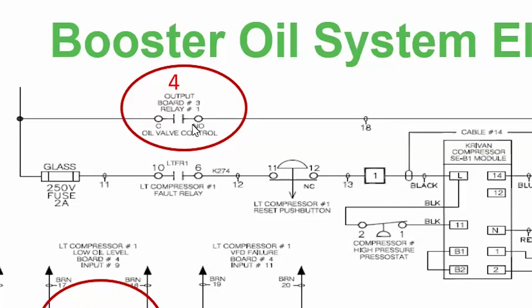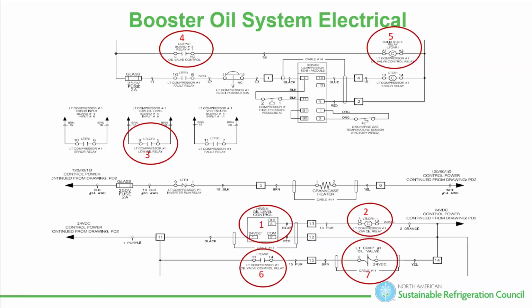If I don't, do I have a bad relay? Is the fuse bad? Because I check voltage here. It could be the fuse on the relay output board, right? And that's how I would find it, because I have voltage here, no voltage here.